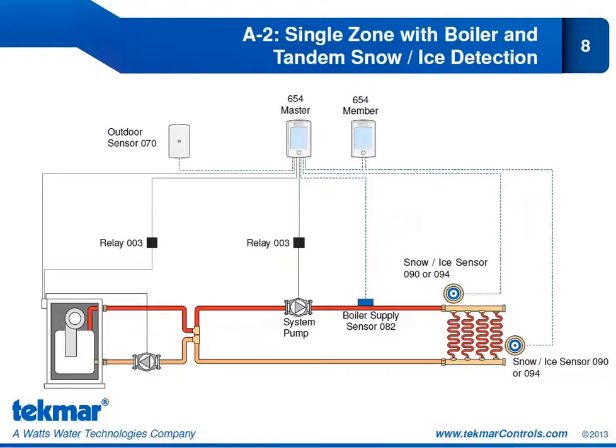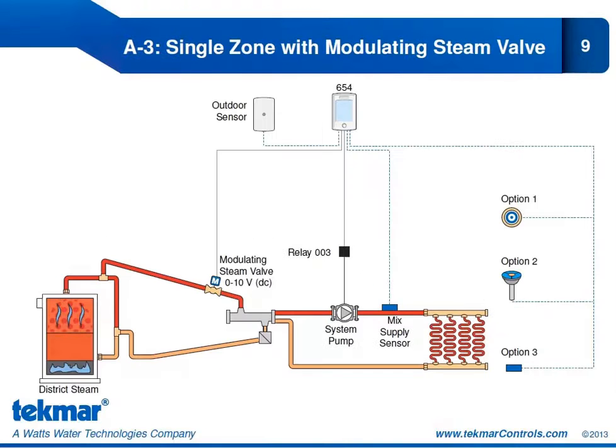Now let's move on to application 3. Application 3 shows a single zone with a modulating steam valve. So in this case, the Snowmelt Control 654 is operating a modulating steam valve and a system pump. The heat source in this case may be either district steam or a steam boiler. And slab temperature is controlled by adjusting the steam valve position using an analog 0 to 10 volt DC or 4 to 20 milliamp signal. So you can see we are using that modulating output to operate the steam valve, and it is the 0 to 10 volt DC or 4 to 20 milliamp signal.